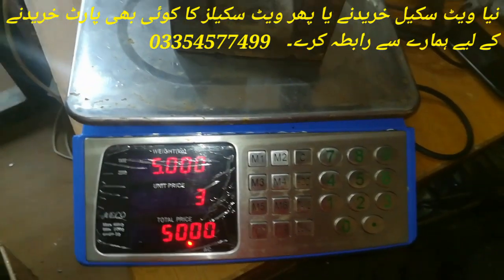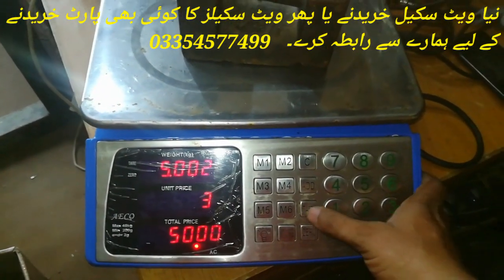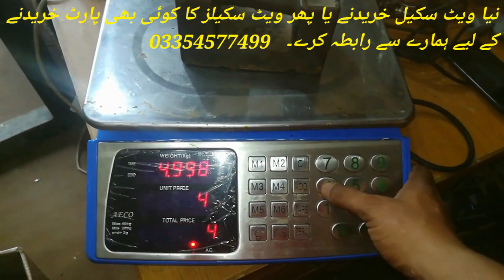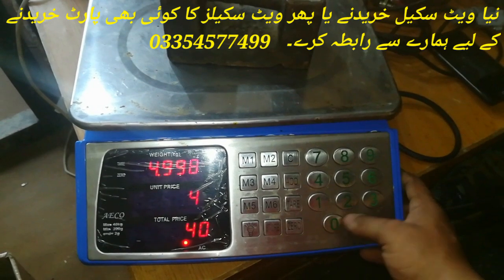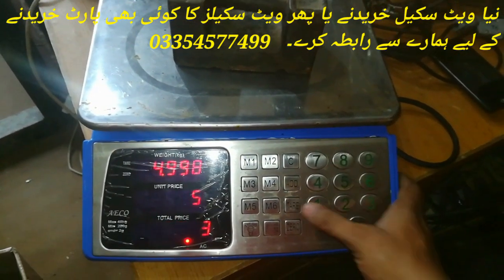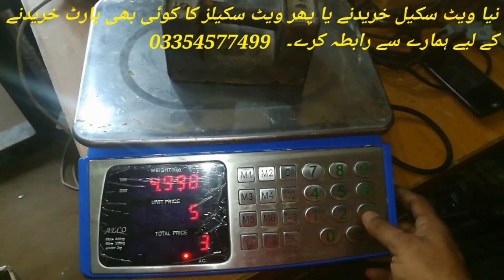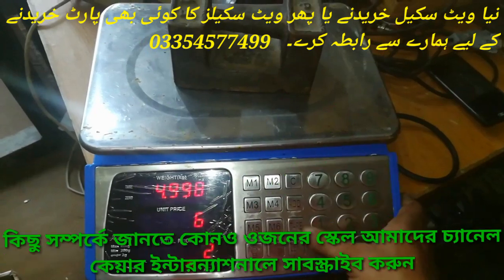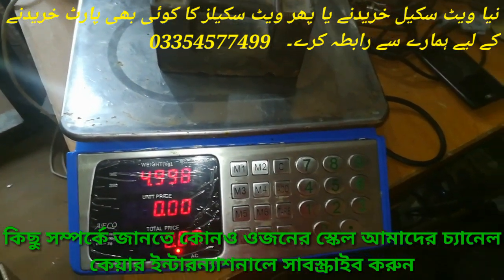We have written 5 kg here and pressed the tare button. Here we have written the total capacity — total capacity is 40 kg — we will write 40.000 and press the tear button. Here we have written 3 and pressed the tare button, then pressed 2 and pressed the tare button. So you can see that the calibration is complete.